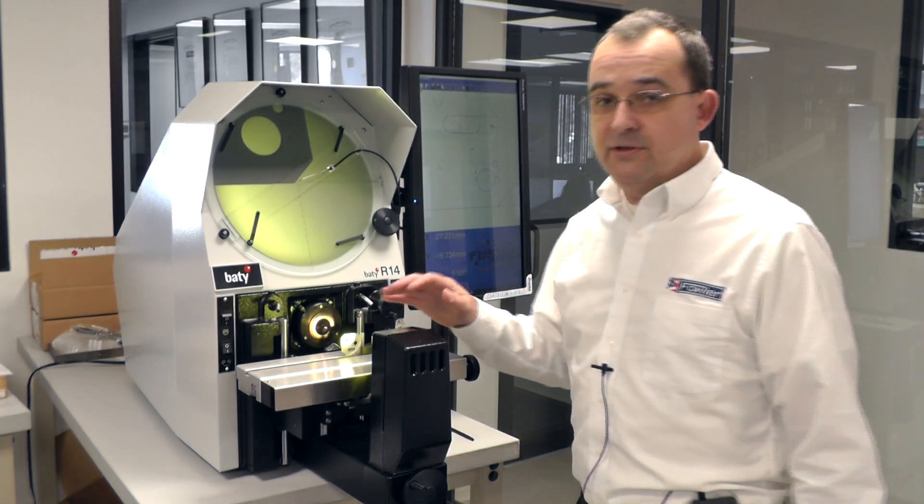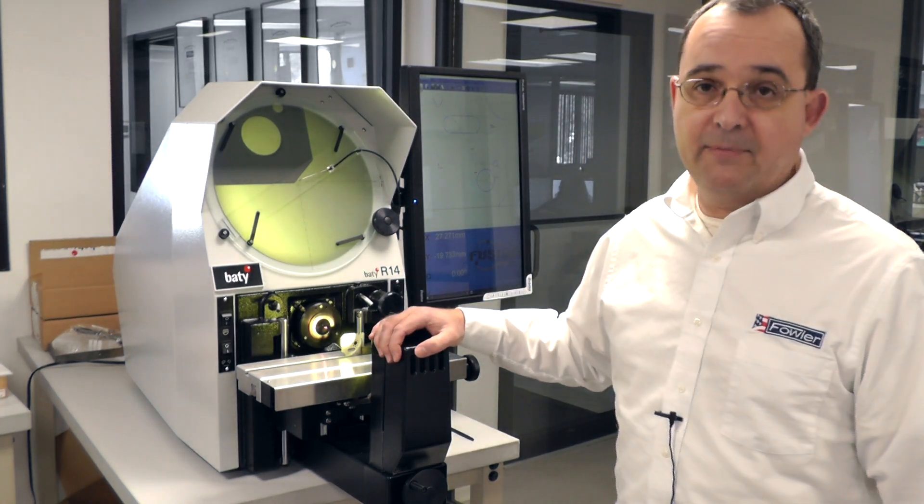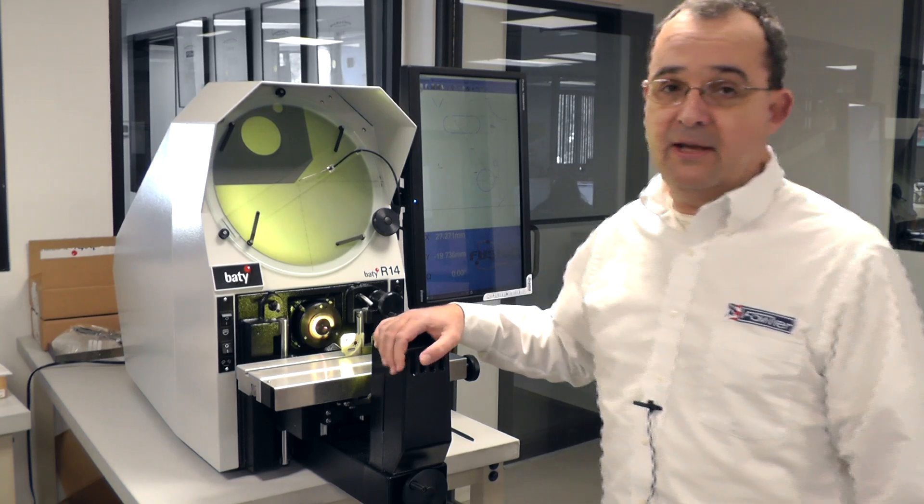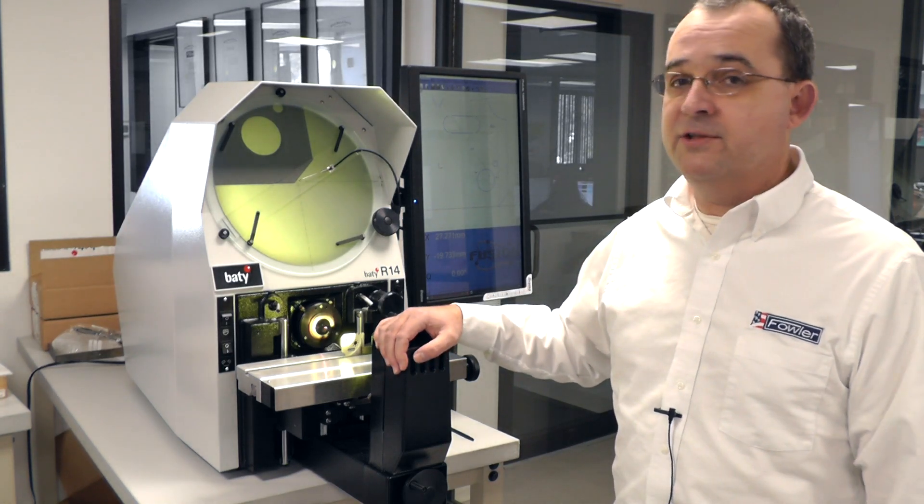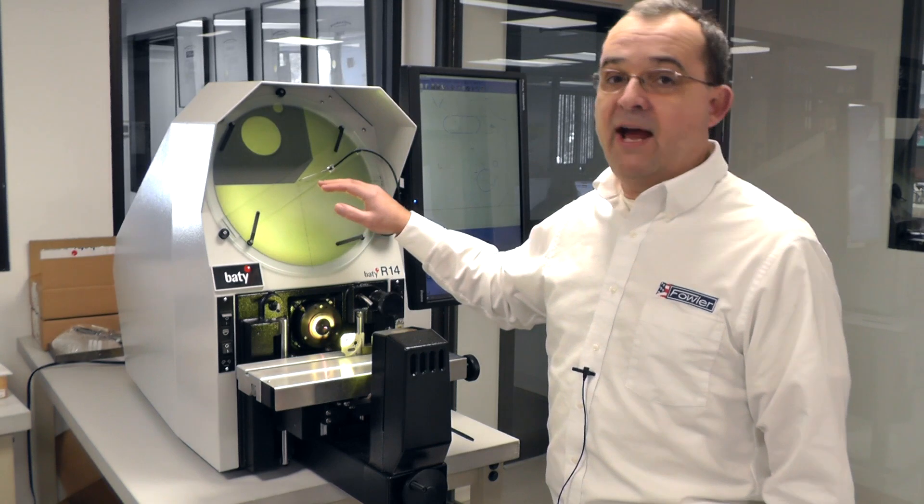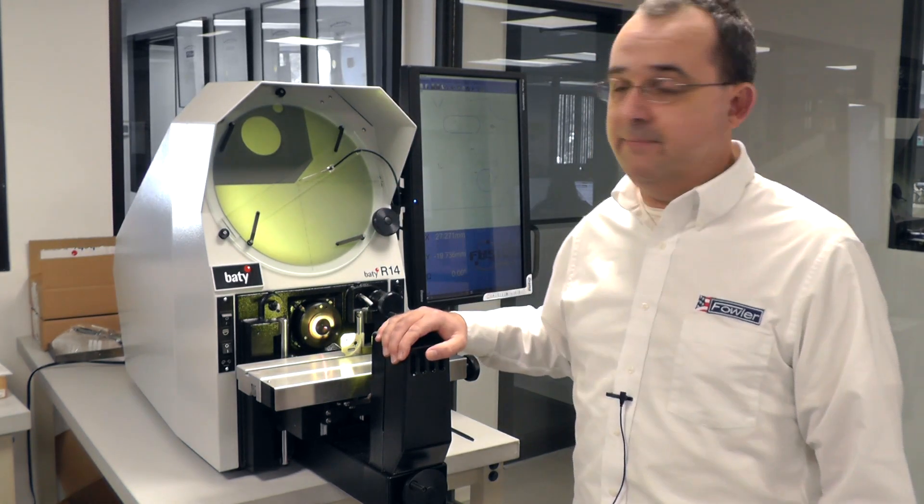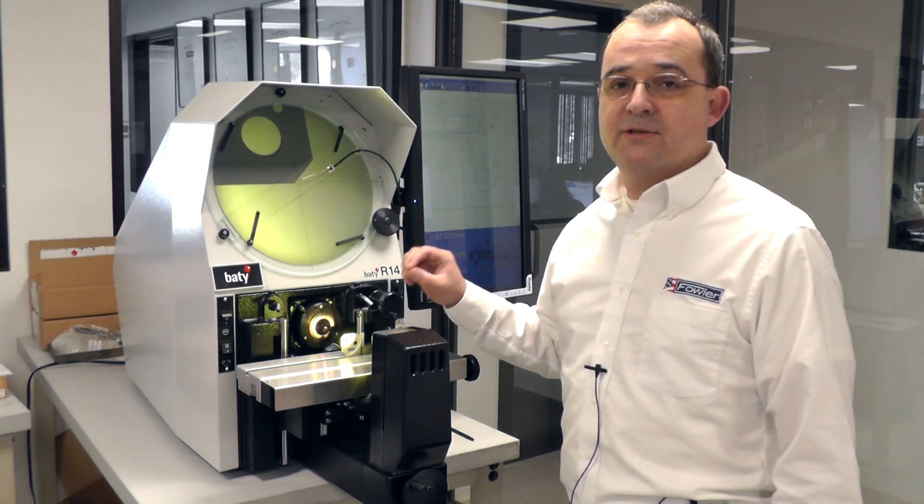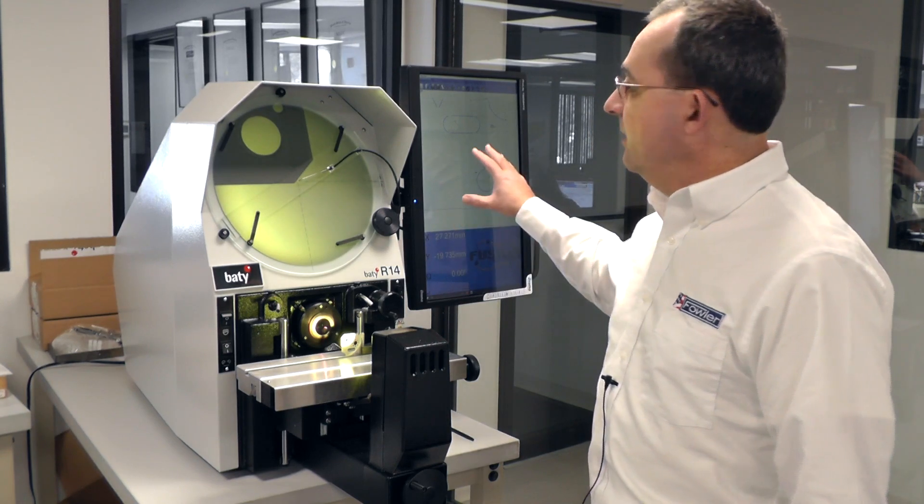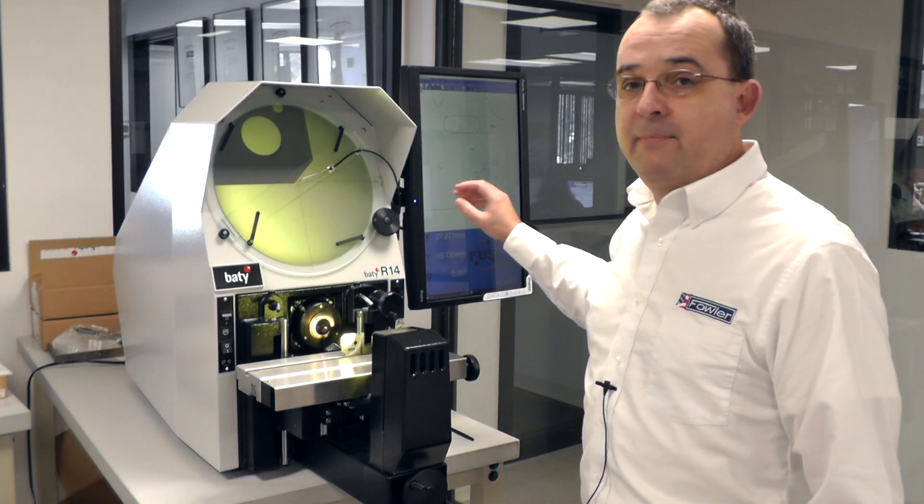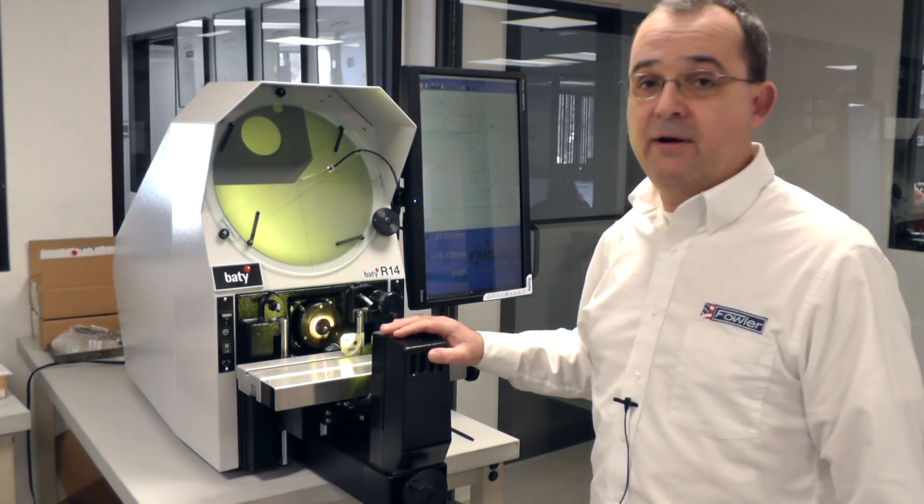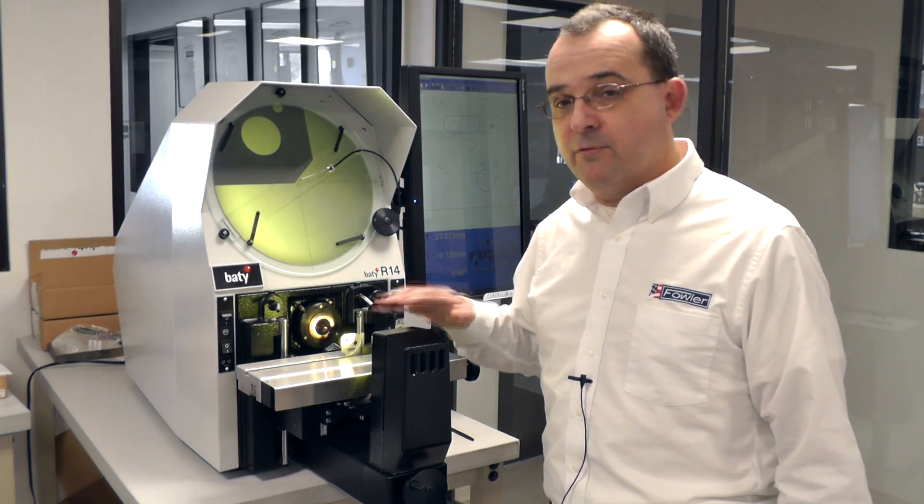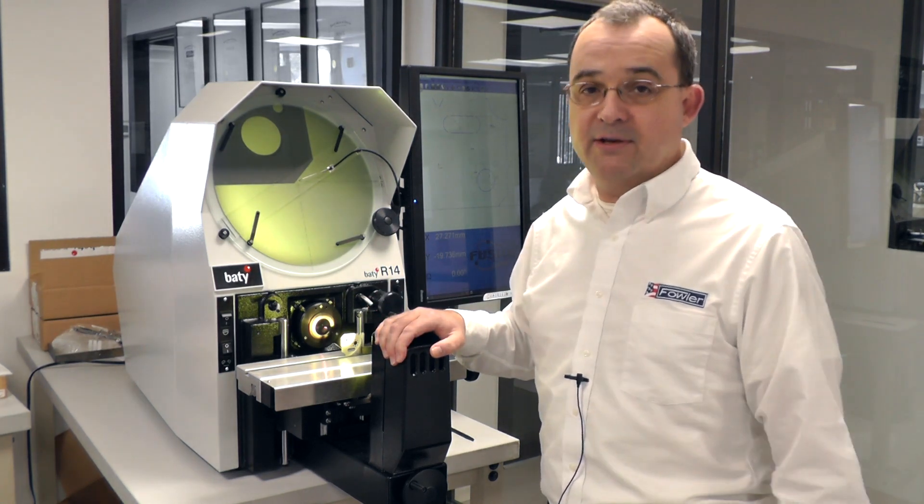Another advantage of the FT2E retrofit is most of the optical comparators on the market today are using an optical edge design that was designed in the 80s. And it is a very old technology. It's not particularly fast. It's made primarily for accuracy using the technology that existed at the time. We have a near zero latency edge detector on here using 32-bit processors that is blazingly fast. We also have the ability to do some very elaborate mapping and error compensation on the comparator itself to tighten up even the sloppiest old comparator so you can get great performance out of something that you may have been considering for the scrap bin.